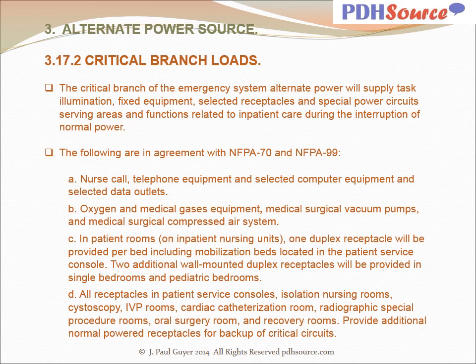Inpatient rooms on inpatient nursing units: one duplex receptacle will be provided per bed, including mobilization beds located in the patient service console. Two additional wall-mounted duplex receptacles will be provided in single bedrooms and pediatric bedrooms. All receptacles in patient service consoles, isolation nursing rooms, cystoscopy, IVP rooms, cardiac catheterization room, radiographic special procedure rooms, oral surgery rooms, and recovery rooms. Provide additional normal powered receptacles for backup of critical circuits.